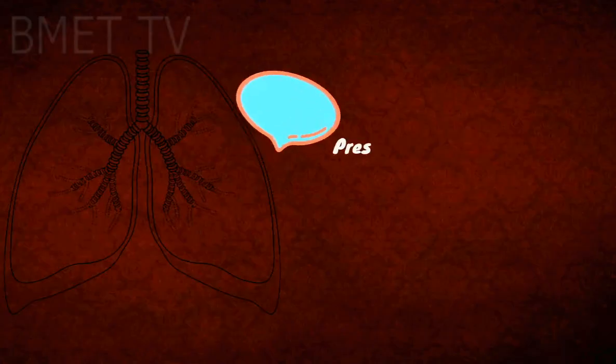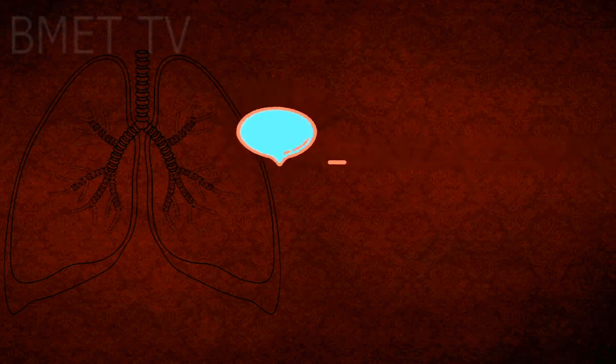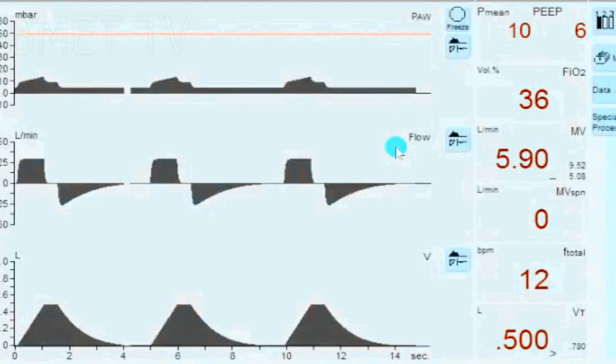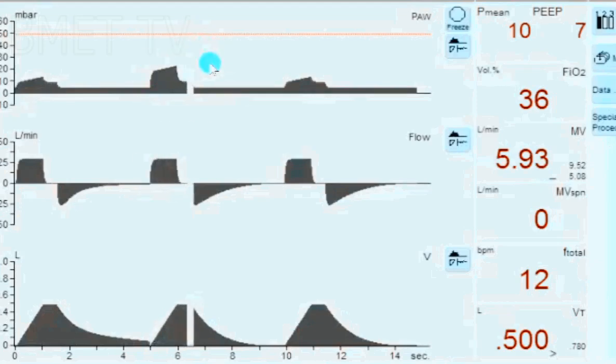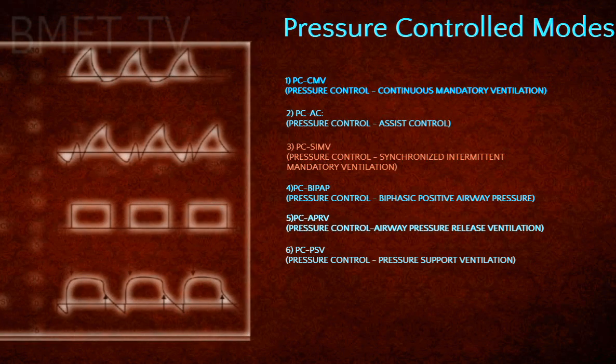The next ventilation method is pressure-controlled ventilation. During pressure-controlled ventilation, two pressure levels are kept constant: the lower pressure level, PEEP, and the upper pressure level, inspiratory pressure. The volume and the decelerating flow are the resulting variables and can vary dependent on changes in the lung mechanics. Pressure-controlled ventilation has different modes. They are as follows: continuous mandatory ventilation, assist control, synchronized intermittent mandatory ventilation, biphasic positive airway pressure, airway pressure release ventilation, pressure support ventilation. All modes are controlled with pressure-related settings.